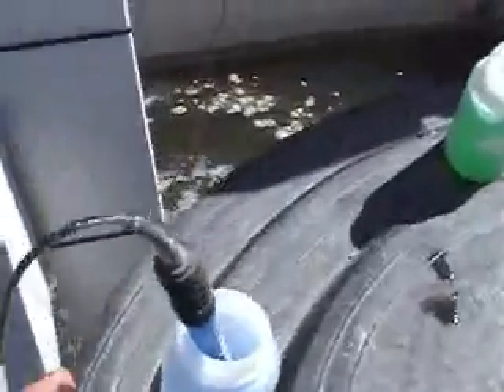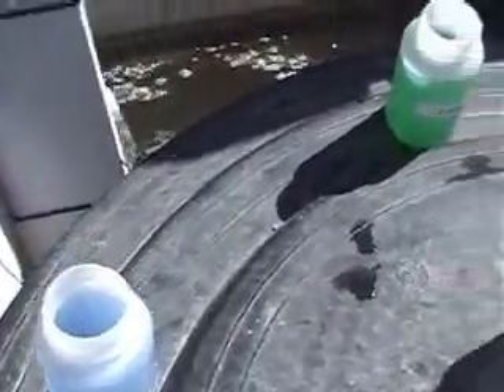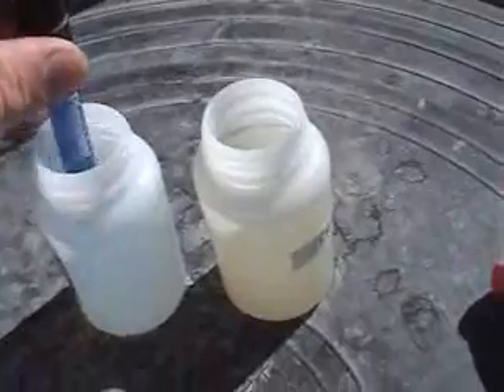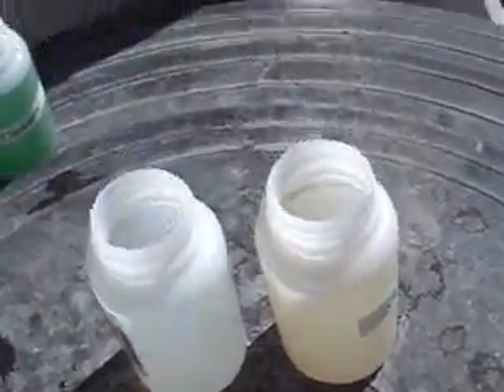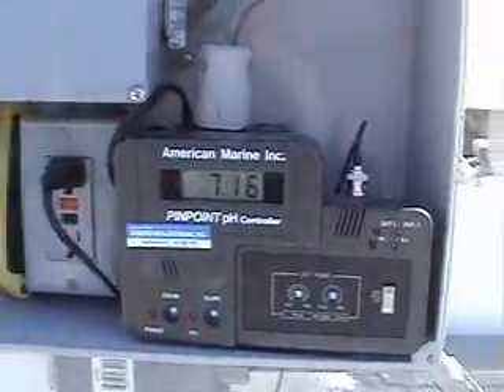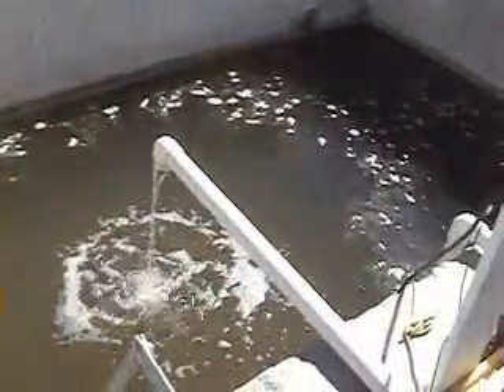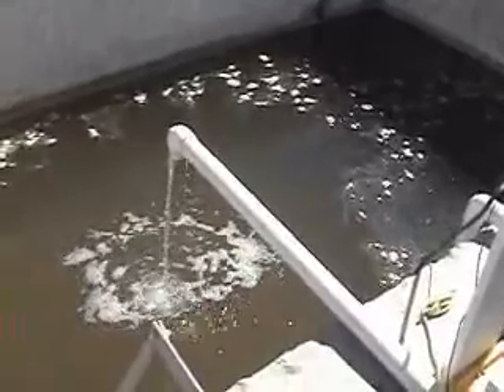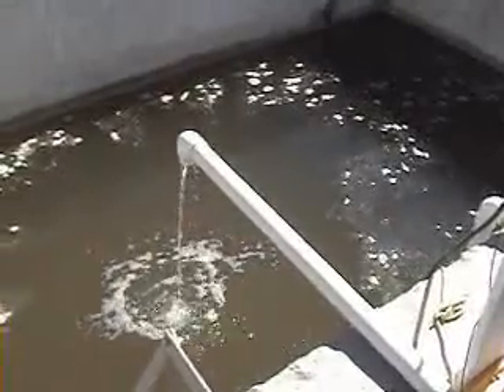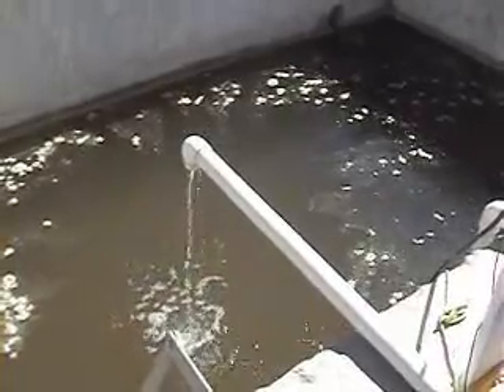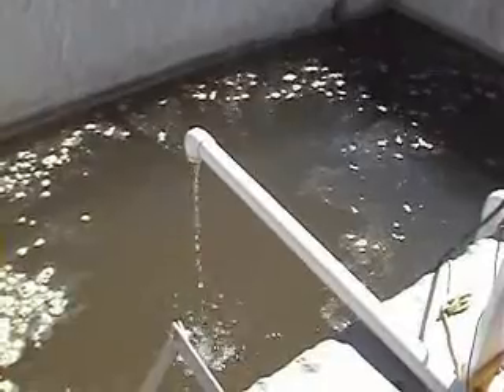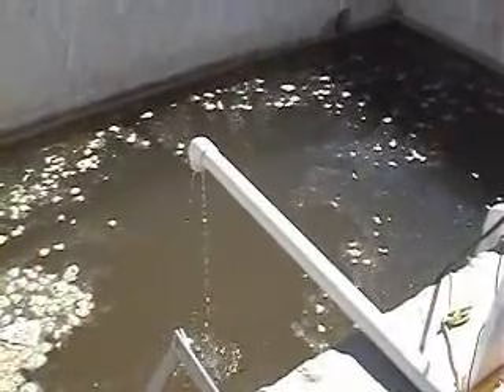Now what we'll do, simply remove our probe from our 10 solution, clean it off, dip it in our diluted water, and then insert it into our 7 solution. Once in the 7 solution, the pH system picks up the acceptable reading, the pump turns off, and the water stops being pumped into our acid storage unit. As you can see, the water flow has just about stopped. Just getting the last little remaining bits out of the drum. And the end result would be something like this, an acceptable pH of right around 7.